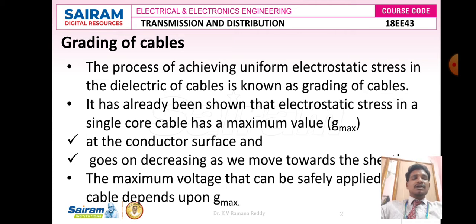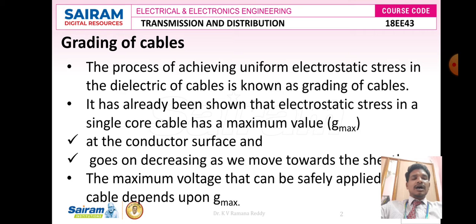These layers protect the cable core from atmosphere, alkalis, acids, and chemical reactions. The process of achieving uniform electrostatic stress in the dielectric of cables is known as grading of cables. The electrostatic stress on the insulating material is not uniform because the core or conductor is surrounded by layers of varying thickness. It has been shown that electrostatic stress in a core cable has a maximum value of Gmax at the conductor surface and decreases as we move towards the sheath or outer layer.